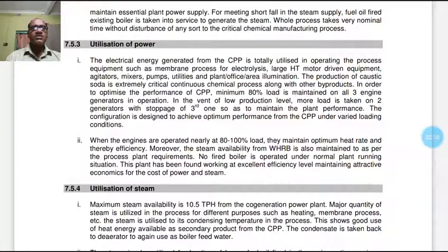Moreover, steam available from the waste heat recovery boiler is also maintained as per the process plant requirement. No fired boiler is operated under normal plant running situation. This plant has been found working at excellent efficiency level, maintaining attractive economies for the cost of power and steam.